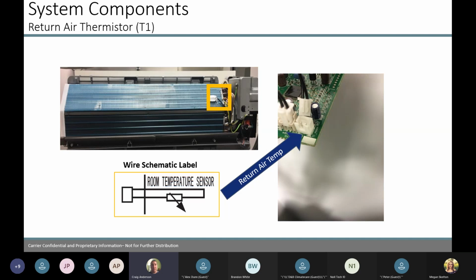Locations of walls adjacent to the unit. Some people put these in mechanical rooms, or they put them in server rooms, where the server room is only 6 feet wide and we're putting a 2.5 ton unit on that wall. The unit is blowing, it's hitting the wall, and it's pretty much just recirculating in there. So what's happening is our compressor is working more than it needs to, turning on, turning off, stuff like that. So airflow is another big thing that's going to affect that thermistor itself. So location is a big thing on that.